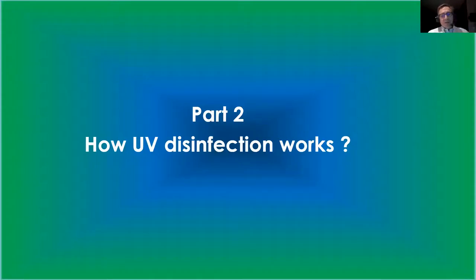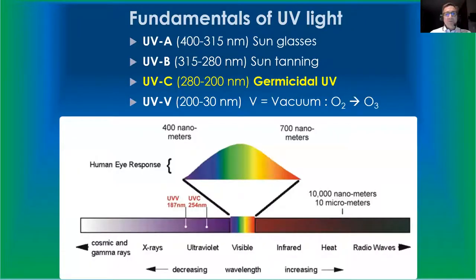So, right into it, how does UV disinfection work? First, I want to show you what is ultraviolet. We have visible light between 400 nanometers wavelength up to 700. That's what we see. Everything else on the infrared side, heat and radio waves, we don't see. And on the left side, ultraviolet, X-rays, cosmic rays, we don't see that either. They have different properties. UVA, you can cut them off with sunglasses. That's reflection on water. UVB is the sun tanning.